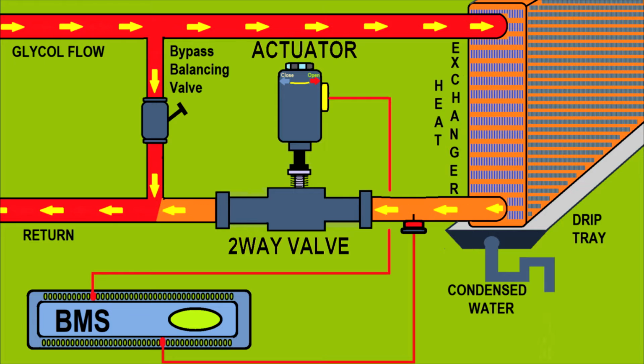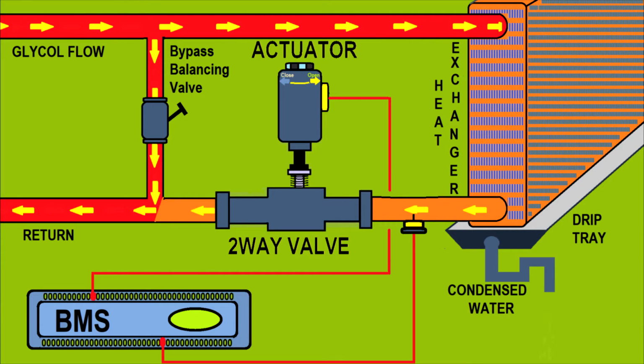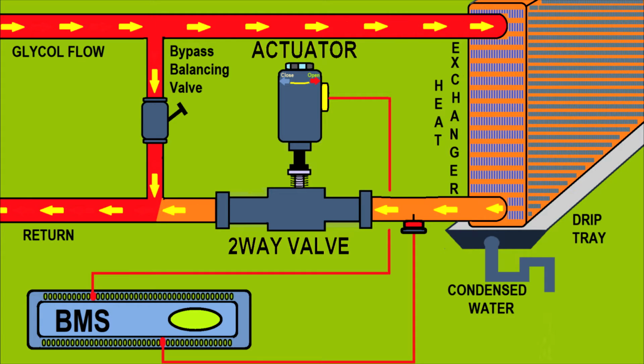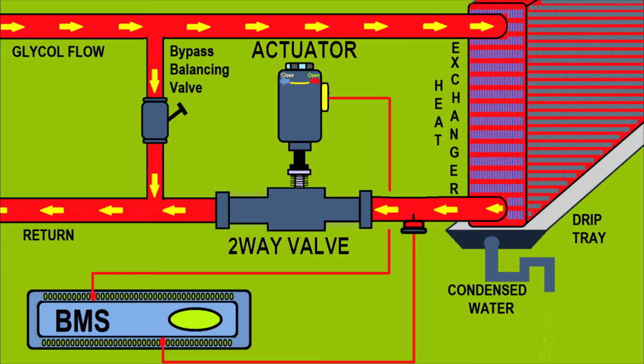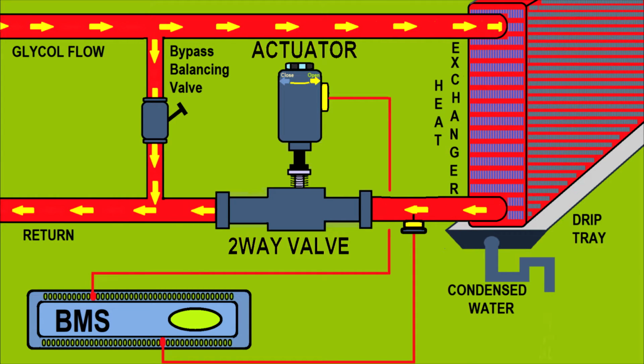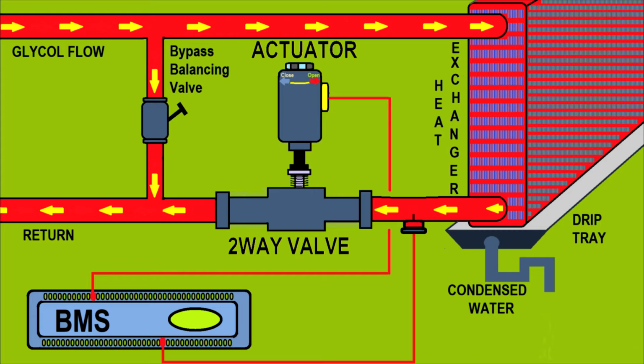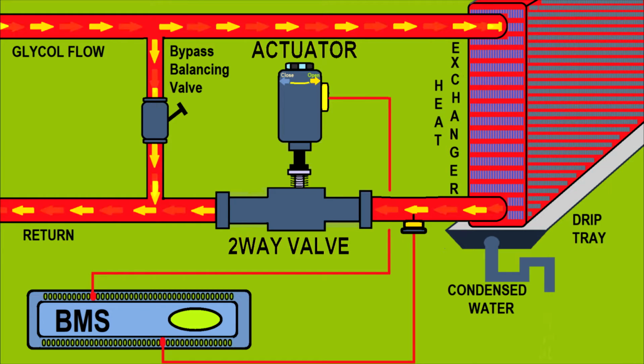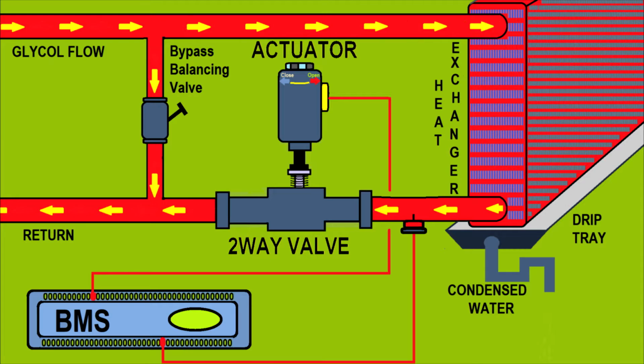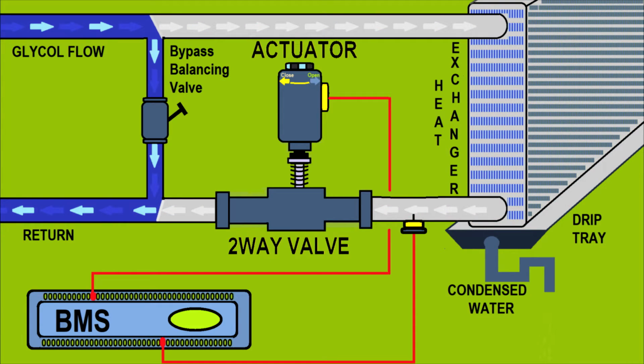Here you'll see how the two-way valve controls the capacity of the heat exchanger, and also you'll see the bypass balancing valves, which allow a specific quantity of heating or cooling agent to pass at any time to balance the entire system. Because think about this, it is just a branch of a huge system, and if you won't have these bypass balancing valves, some areas will be starved and some areas will get more than they need to heat or to cool the premises.